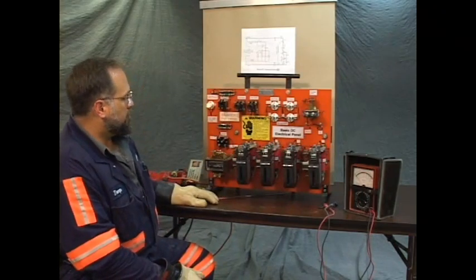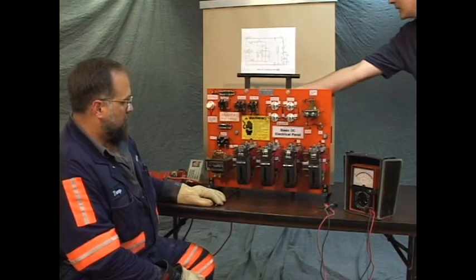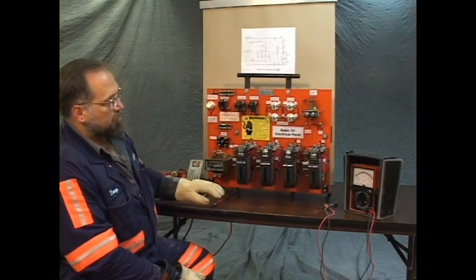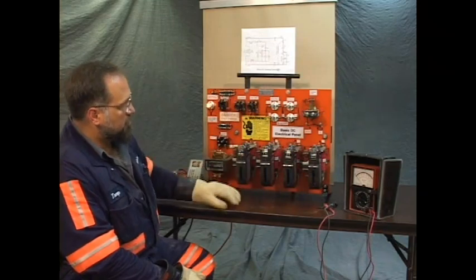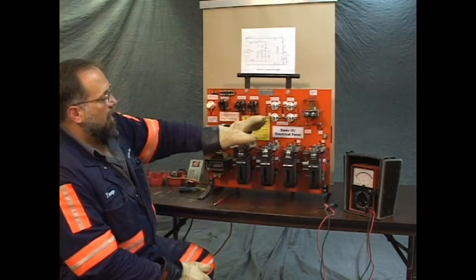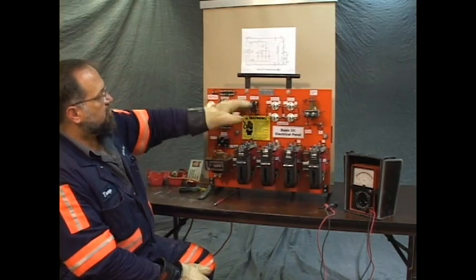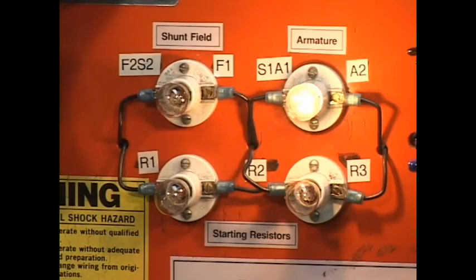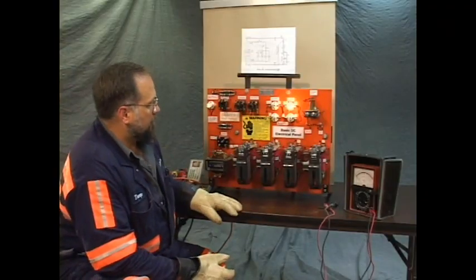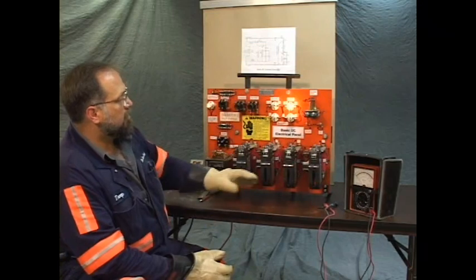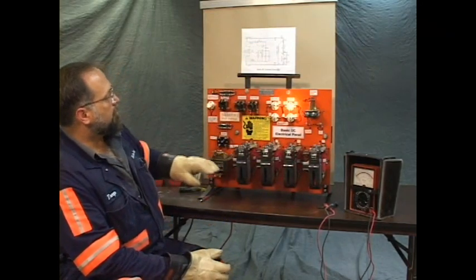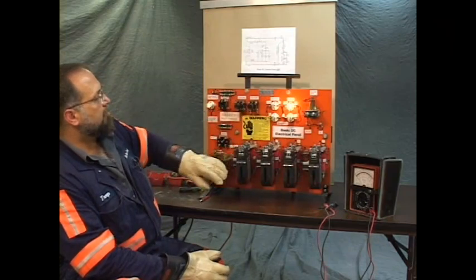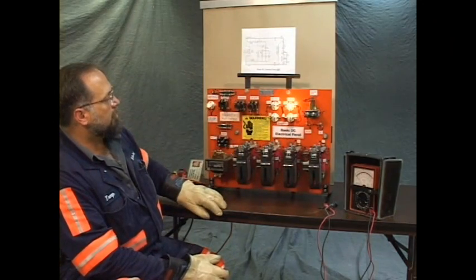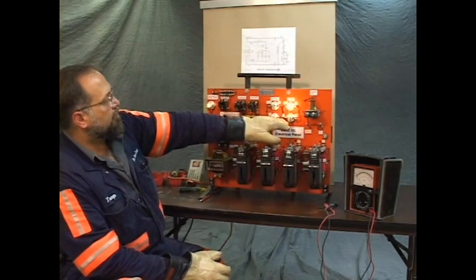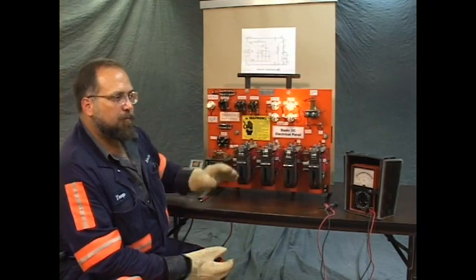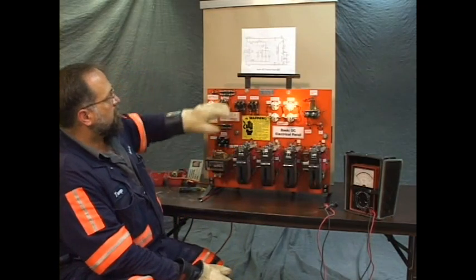Now let's install the problem. Let's toggle the switch. As the problem stated, all the control works normally. They all close in proper sequence, and they hold. You can turn loose the start switch, but the shunt field doesn't light up. And the control operates correctly. You have M1 and M2 going in simultaneously, 1A and 2A, proper order. These 3 lights came on dim. When 1A closed, the R1, R2 light went off. When 2A closed, the R2, R3 light went off, and the armature is very bright. The only part of the circuit that didn't work is the shunt field.